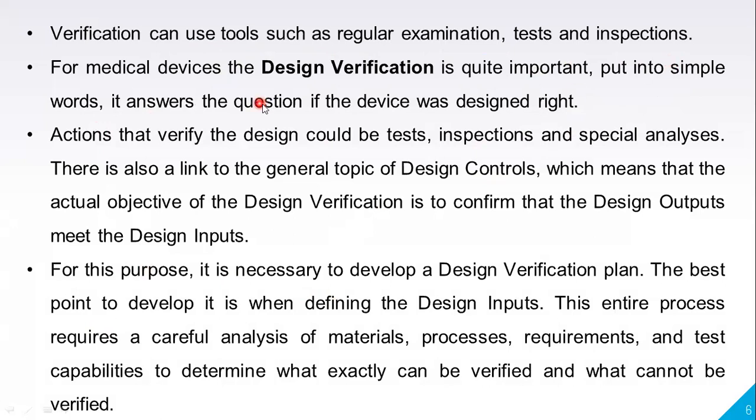For medical devices, the design verification is quite important. Put into simple words, it answers the question of whether the device is designed right. Actions that verify the design could be tests, inspections and special analysis. There is also a link to the general topic of design controls, which means that the actual object of design verification is to confirm that the design outputs meet the design inputs.